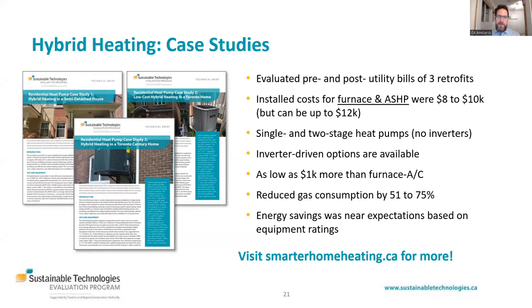These systems utilize single and 2-stage heat pumps. They weren't inverter driven, although there are inverter driven options available. I'm not going to get too technical, but inverter driven options are a bit more flexible and more efficient, with the ability to ramp up from almost 0 to 100%.